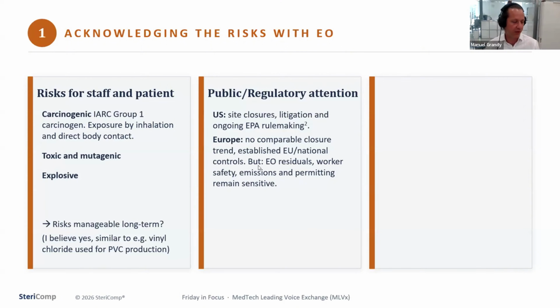And I can give you a few examples also in Europe. For example, currently two of my clients from Europe, in the same country, are both extending their EO sterilization capacities. They built a new chamber. Even though it's in the same country and pretty much the same case, different authorities are checking them. So for one, it's relatively smooth. I mean, they still have to keep the rules and so on, but it's relatively smooth. And the other one has to do tons of paperwork and has already a year of delay because of the permits. So permitting is getting more difficult because EO, carcinogenic and so on, could be a red flag. Okay. So there are also risks definitely in Europe.